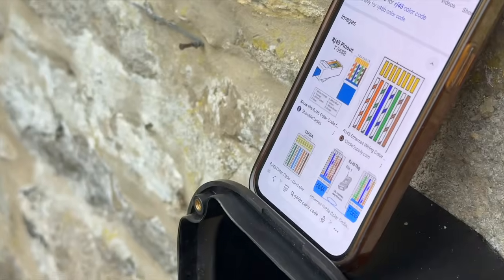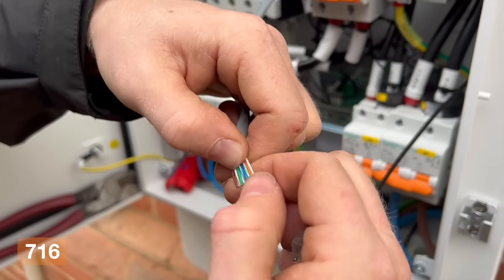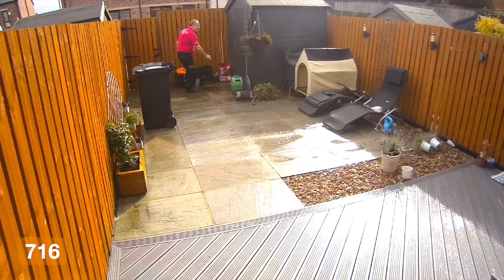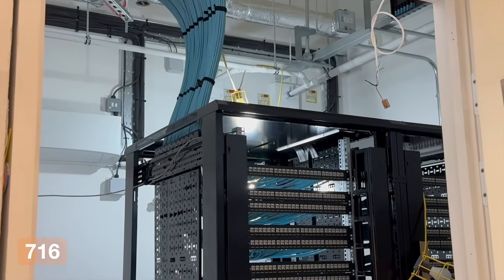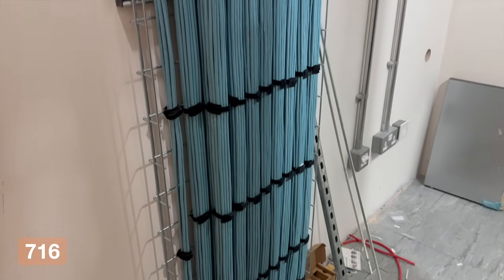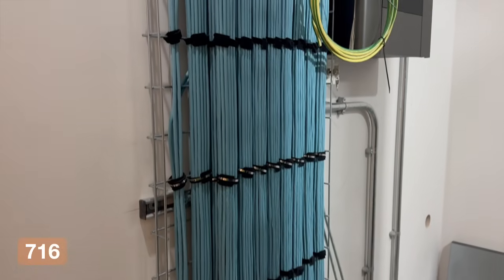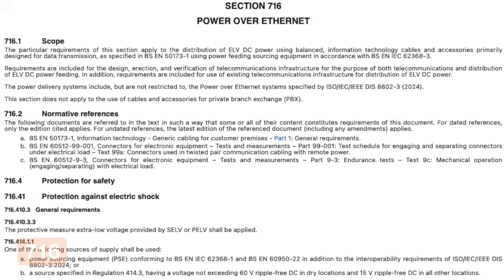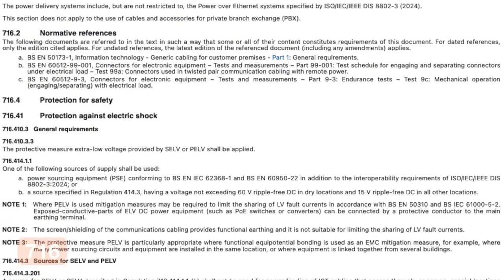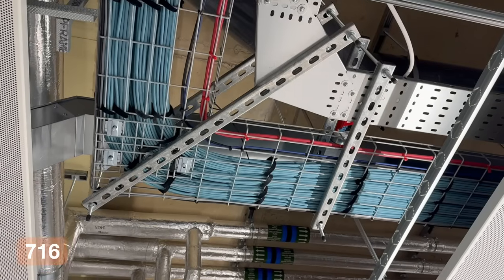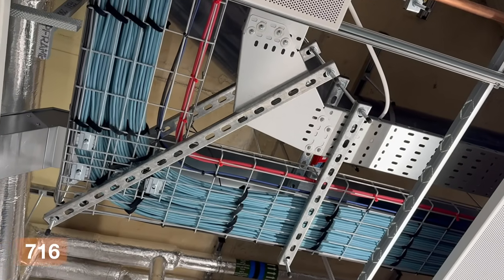Power over Ethernet is now formally covered in BS 7671 under section 716. Before getting into the regulations, it's worth being clear what this actually is. This is where a single cable is used to provide both power and data. You will typically see these on things like CCTV cameras, Wi-Fi access points, and other networked equipment around a building. So what used to be just a data cable is now also part of the power distribution system. And that is why it now sits within the scope of the wiring regulations. The system operates at extra low voltage using SELV or PELV. And the regulations now go a step further in defining exactly how that supply must be provided.